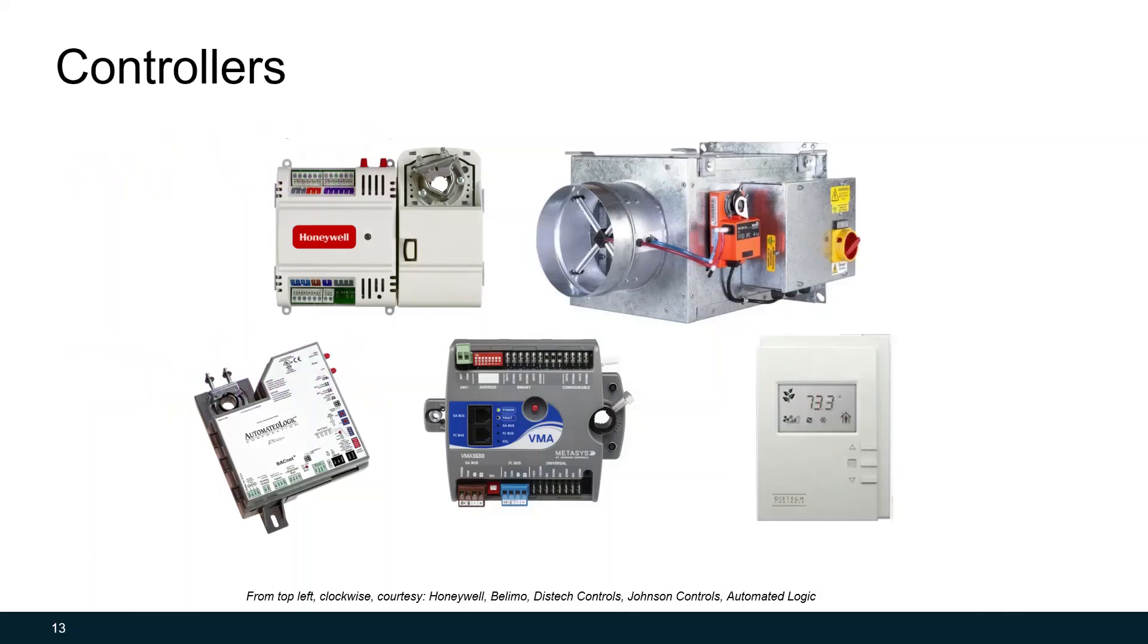Here's a picture of some more controllers. In the top right of your screen, you'll see an air terminal box, commonly seen in variable air volume systems. What's important to note here is that it comes with a pre-packaged controller. When you're specifying equipment, make sure that you know whether or not it comes with its own controller. If it doesn't come with its own controller, you might need to specify a separate controller from the controls contractor to go with it. In the bottom right, you'll see a thermostat, which is also a sensor, but does include a controller. In your home air conditioning system, the thermostat is the controller that is sending an output signal to your furnace or air conditioning unit to turn on and off.